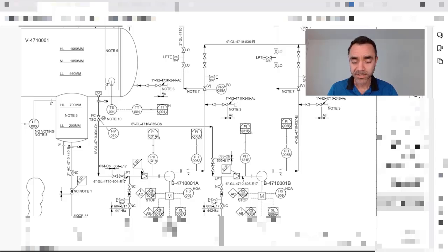Going to the pump, you can see this symbol here that represents usually a strainer. It can be a temporary strainer or an operational, permanent strainer. In any case, in this installation we have a pressure indicator transmitter that sends a signal to the control room, where the pressure indicator has an alarm of low pressure. This is important because once I have a strainer here and it can block, it will not block from one day to another.